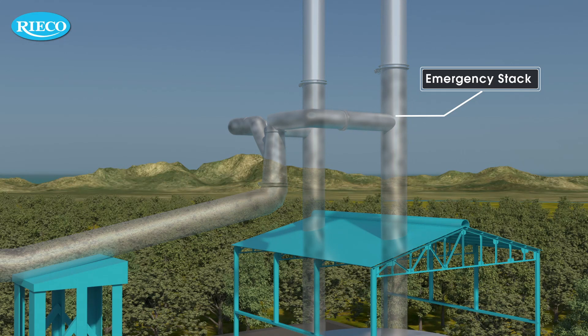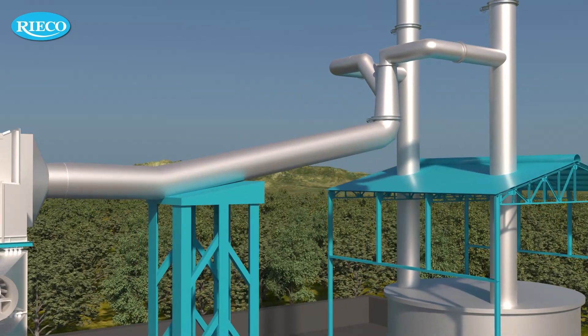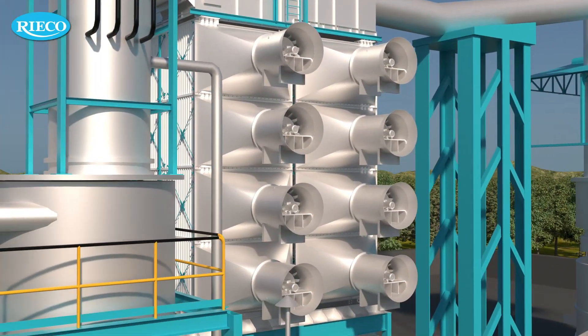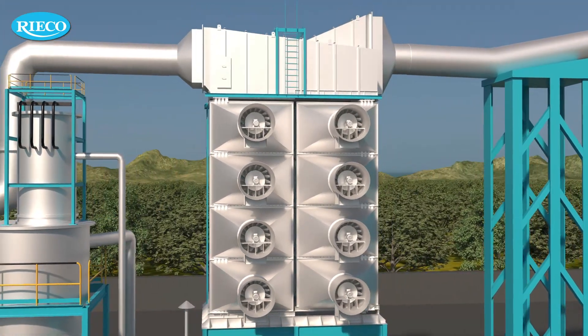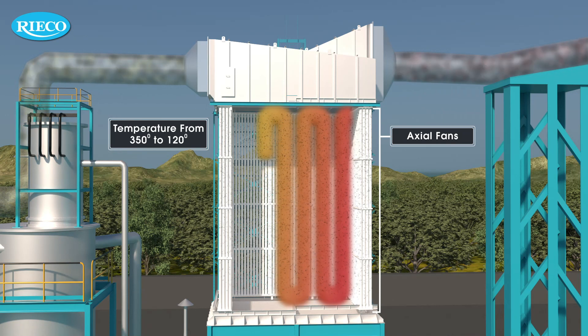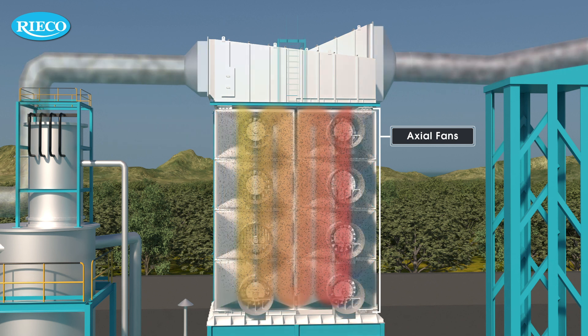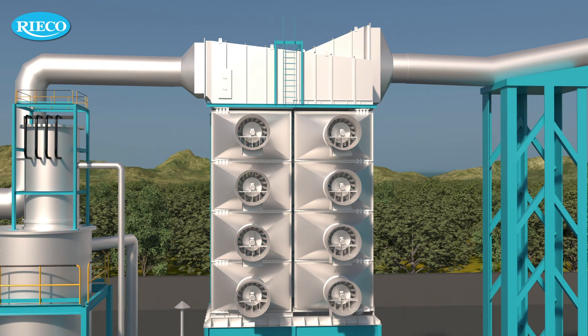The ID fan at the downstream of the system creates suction, resulting in the extraction of fumes to RIECO's fume extraction system. High temperature fumes pass through the heat exchanger. The axial fans reduce the temperature from 350 degrees Celsius to 120 degrees Celsius. An interlock is set which facilitates saving of operational cost of the system.